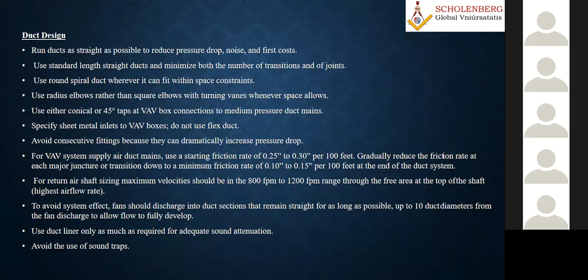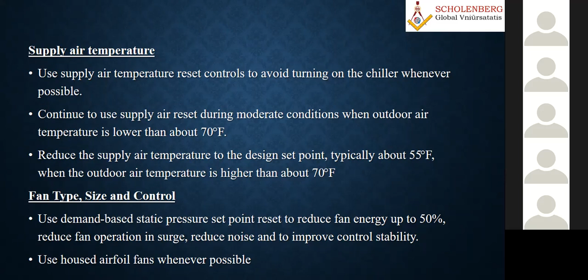So the supply temperature approximately we know, and the demand, fan static pressure, we normally select the fan accordingly. Fans and blowers are basically another important topic which I told you. You have different kinds of fan. Centrifugal fans, generally we use as blowers. We don't call them fans, we call them blowers; we call them axial fans. Axial fans also, vane axial, tube axial, and most of these axial fans are used for exhaust because each has its own characteristics. But when it comes to air handling units, we use a blower. It can be backward curved or forward curved or normal curved. Everything has its own plus and minus, and the standard specifies it also.